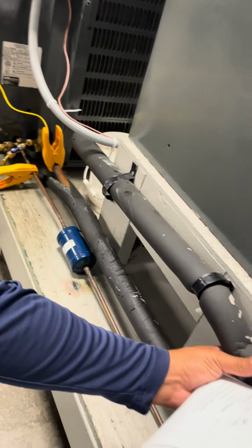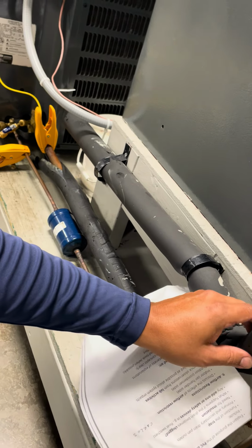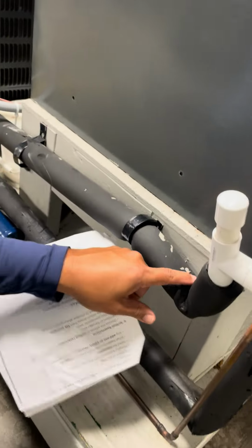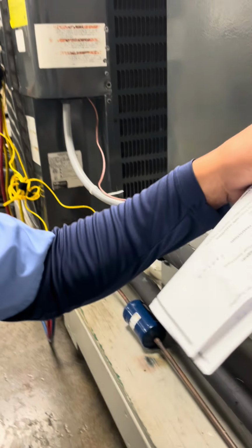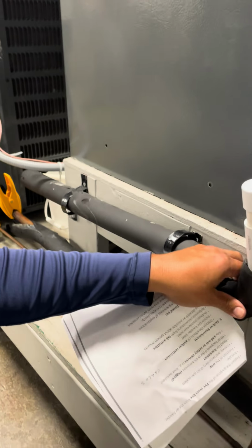Also, next we're talking about the condensate drain line system and what it's for. It's mainly to allow the moisture that's created and the humidity that builds up in the system to drain. The pipe is normally designed like a P-trap style to allow water and moisture to seep out, but it also prevents bad fumes from going back into the air handler system. So we should always make sure there's water in the P-trap section.